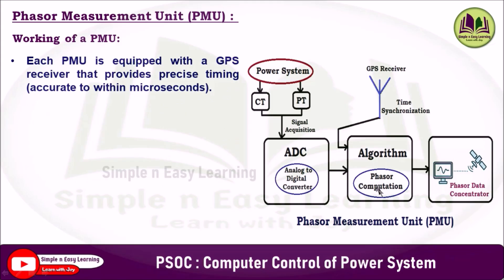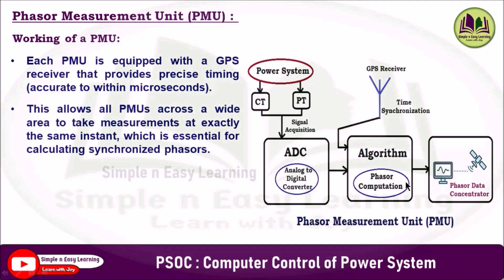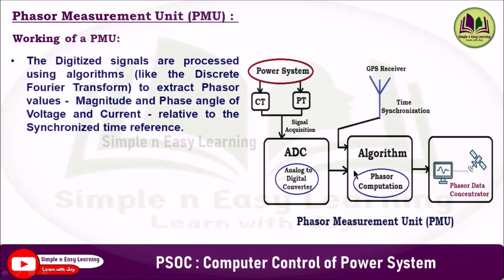Each phasor measurement unit is equipped with a GPS receiver that provides precise timing accurate to within microseconds. This allows all phasor measurement units across a wide area to take measurements at exactly the same instant, which is essential for calculating synchronized phasors. The digitized signals are processed using algorithms such as the Discrete Fourier Transform, Kalman filter method, matrix pencil method, and least squares method — which is also used in state estimation — to extract phasor values like magnitude and phase angle of voltage and current relative to the synchronized time reference.